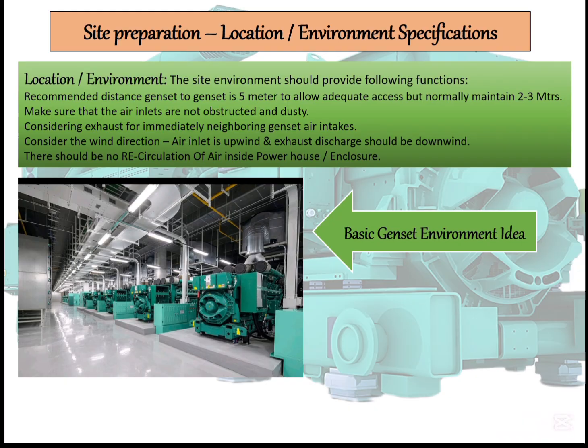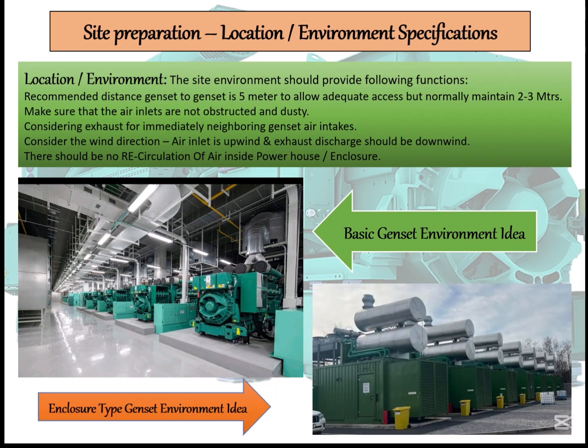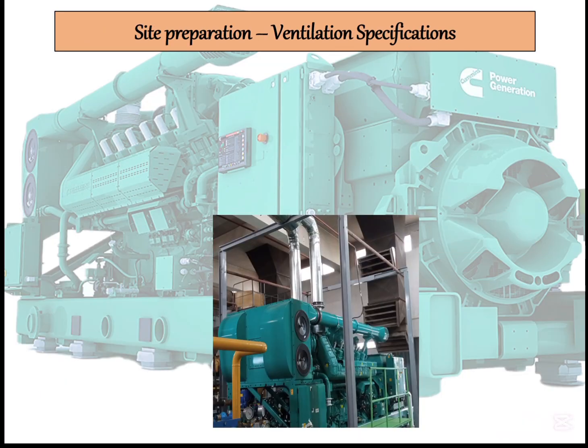This is a practical powerhouse. You can see how it is, then the genset-to-genset distance and installations. Then this is a typical enclosure-type genset where you can see the environment is clean. We cannot say the genset cannot run in a dusty environment, such as mining areas where dust is a concern. Yes, it can run, but we need to take some preliminary actions like filtration and others, so we get fresh, clean air for combustion and cooling purposes.